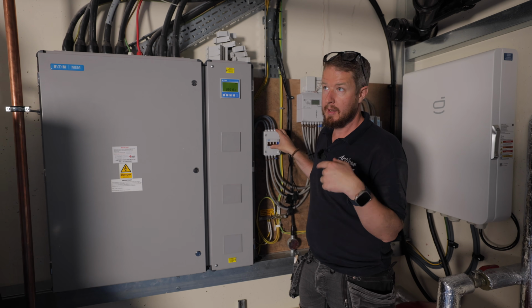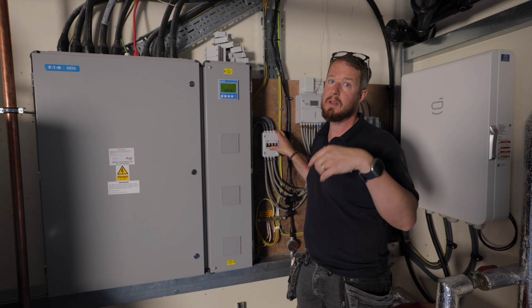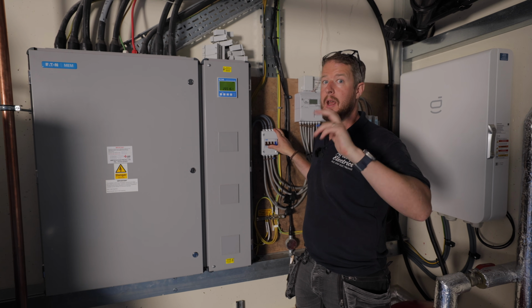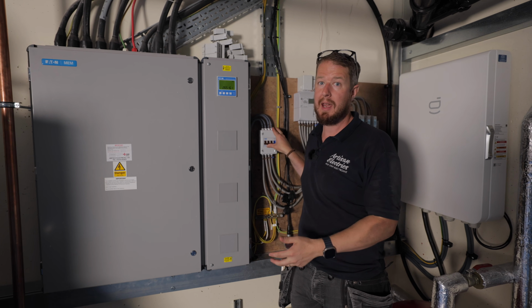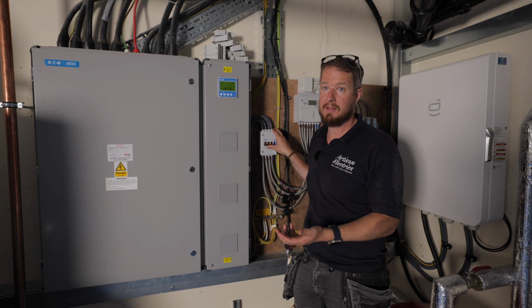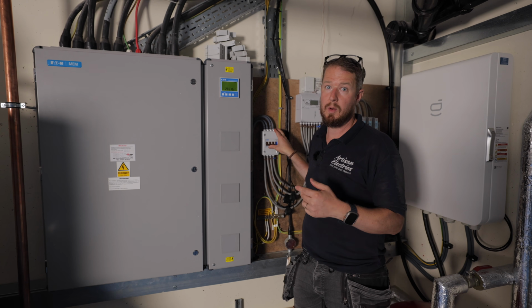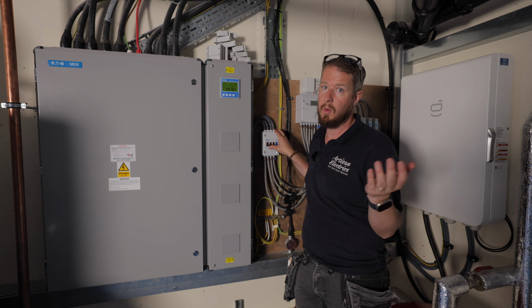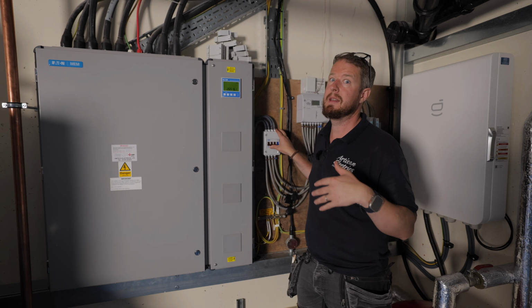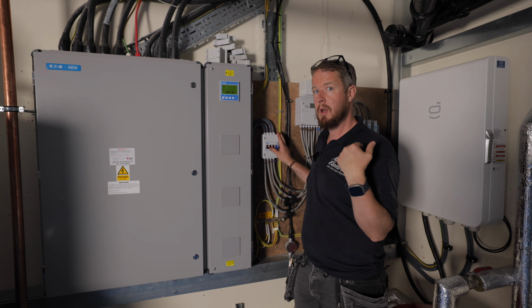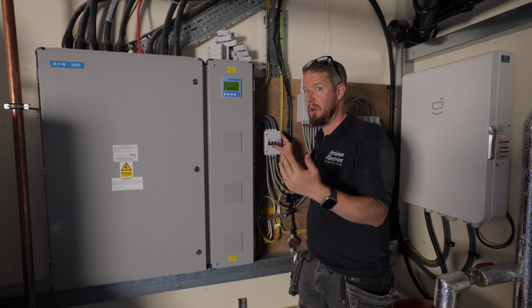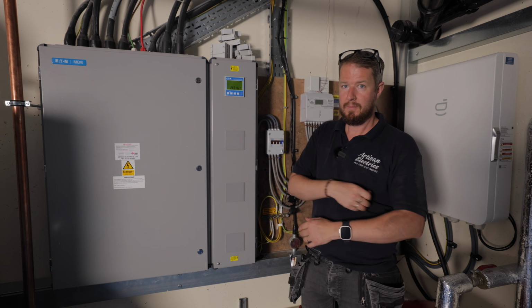What we should hear is after a few seconds or minutes, the contactor switches in and switches us back over. It doesn't do that instantaneously because sometimes you have a flicker on the grid where it flicks on and off again, and you don't want it to destabilize things. So it will wait until it's got a reliable grid connection before clicking in. Let's see if I'm right.